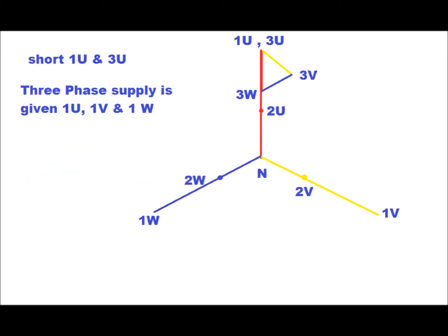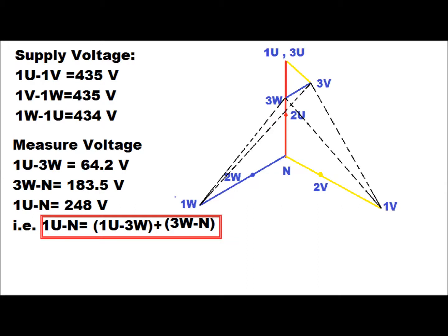For the vector group test, we short 1U and 3U — that is red phase of primary winding with red phase of tertiary winding — and three phase supply is given to the 1U, 1V, 1W terminals, that is red, yellow, and blue phase of the primary winding. The supply voltage measured between red-yellow, yellow-blue, and blue-red phases is 435 V, 435 V, and 434 V respectively.